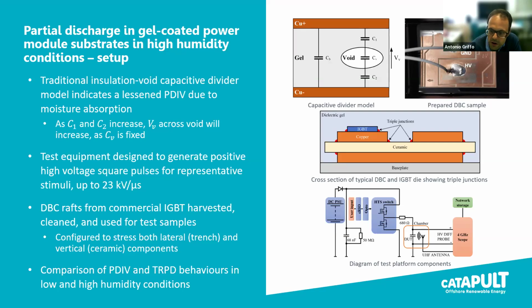To understand this phenomenon, we have constructed this test platform shown in the figure on the right, where we can create a high voltage dV/dt of up to 23 kilovolts per microsecond transient applied to the dielectric substrates on DCB rafts commonly used on standard 1.7 kV IGBTs for wind turbine. Next, please.